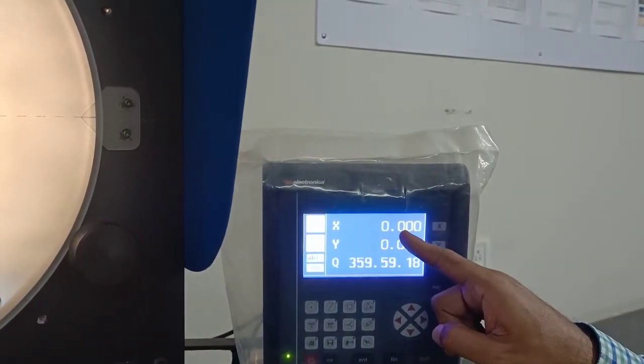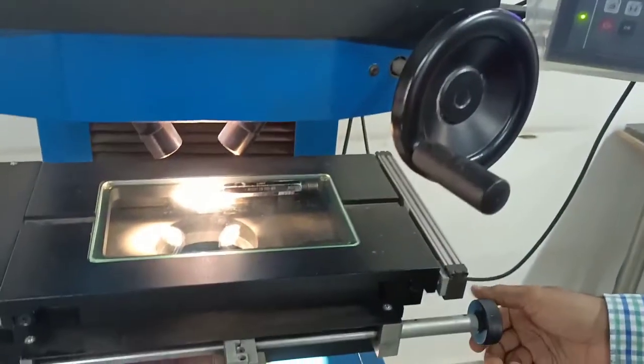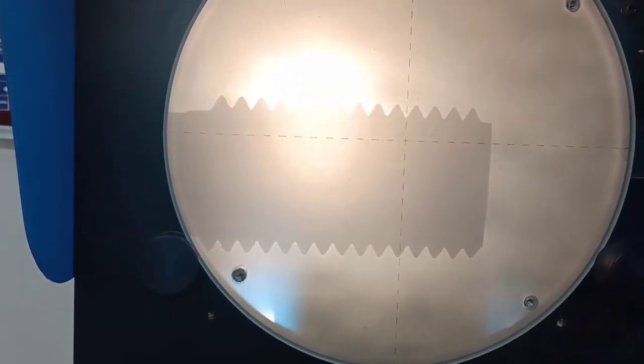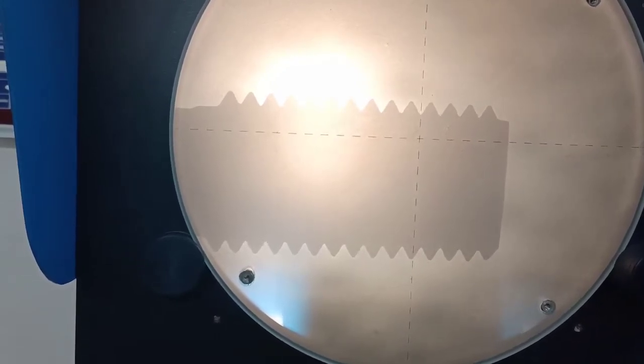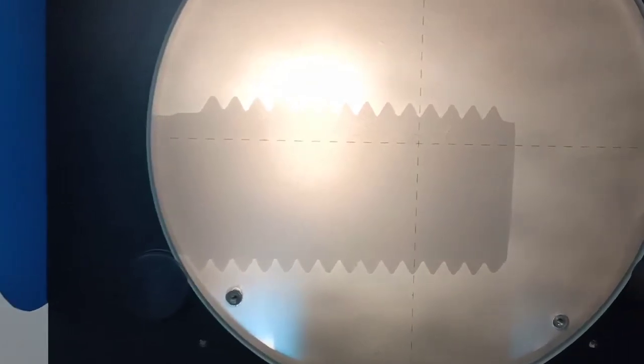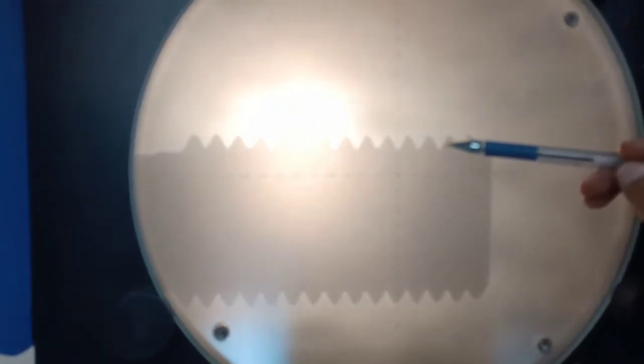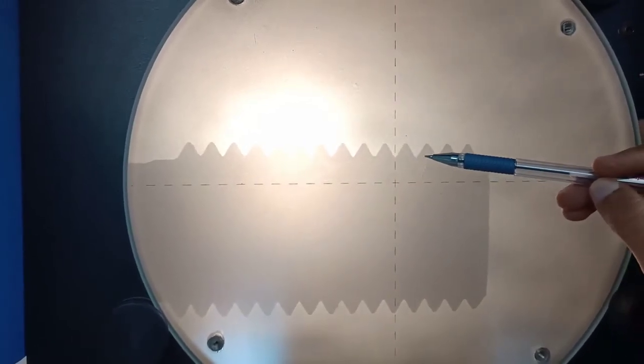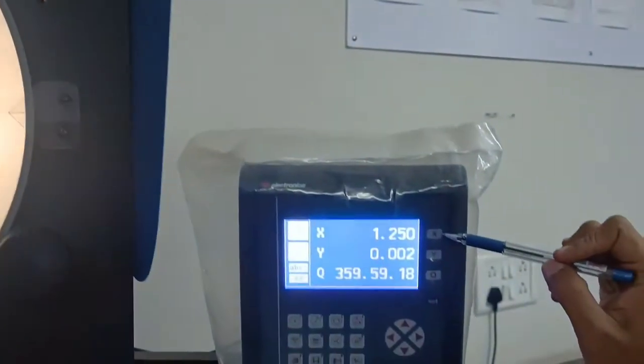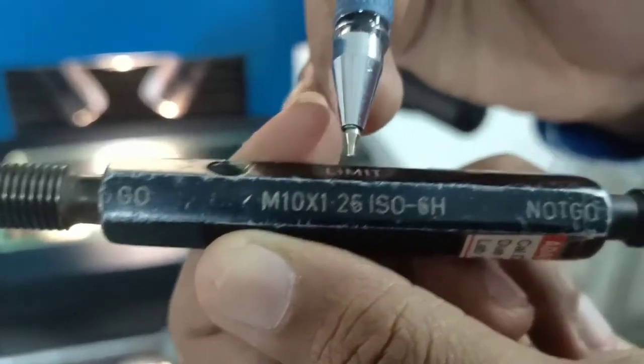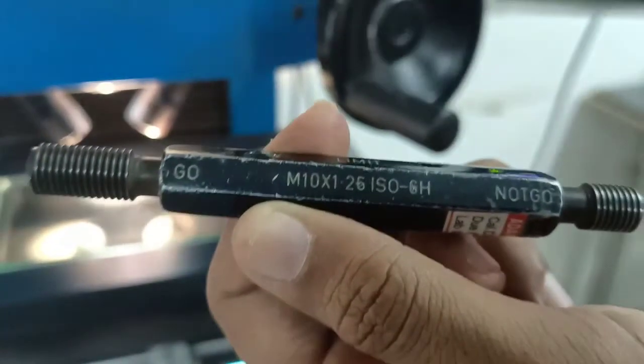What you have to do is set X to zero. I have set it to zero now. Then you have to move the table so that it touches the next root point. Here comes the next root — I have moved the shadow from this point to this point, and this becomes the pitch. If you observe, X has moved to 1.250 mm. So this is the pitch of this thread. Looking at the thread gauge specification, the pitch is mentioned as 1.25mm — and this instrument is also giving us a 1.25mm reading, showing very high accuracy.